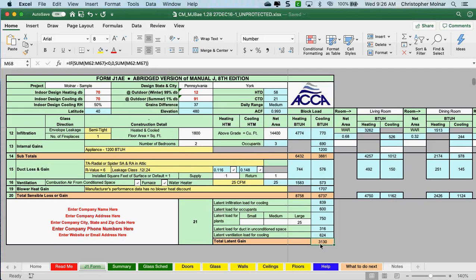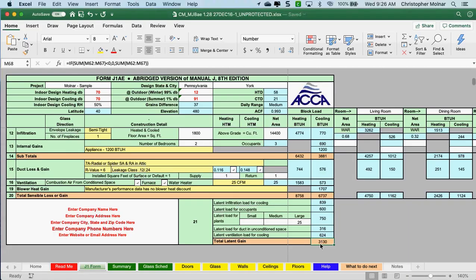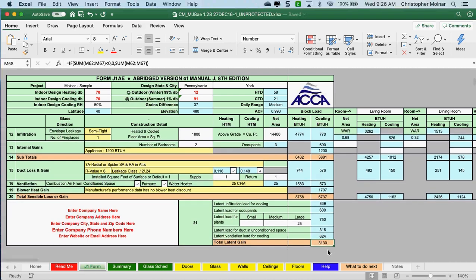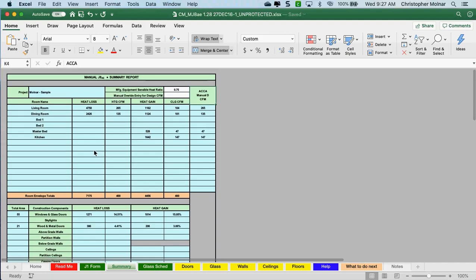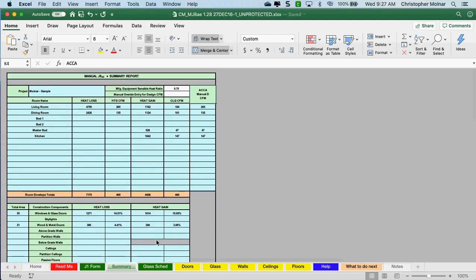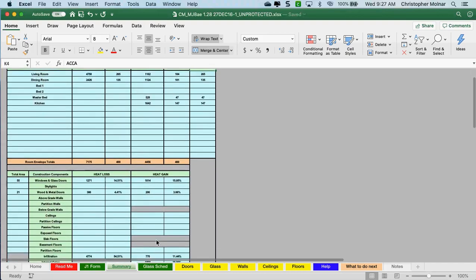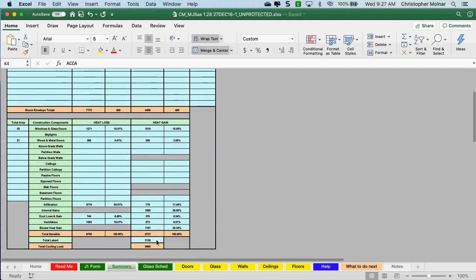When I'm sizing equipment and looking at units, I have to have both. Once you get your values all the way down and your room-by-room is done, this form J1 is done. You can come over to the summary page. You're going to have heat loss and heat gain, and you need to find your total sensible cooling load, your total latent, and your total cooling load for the entire building.